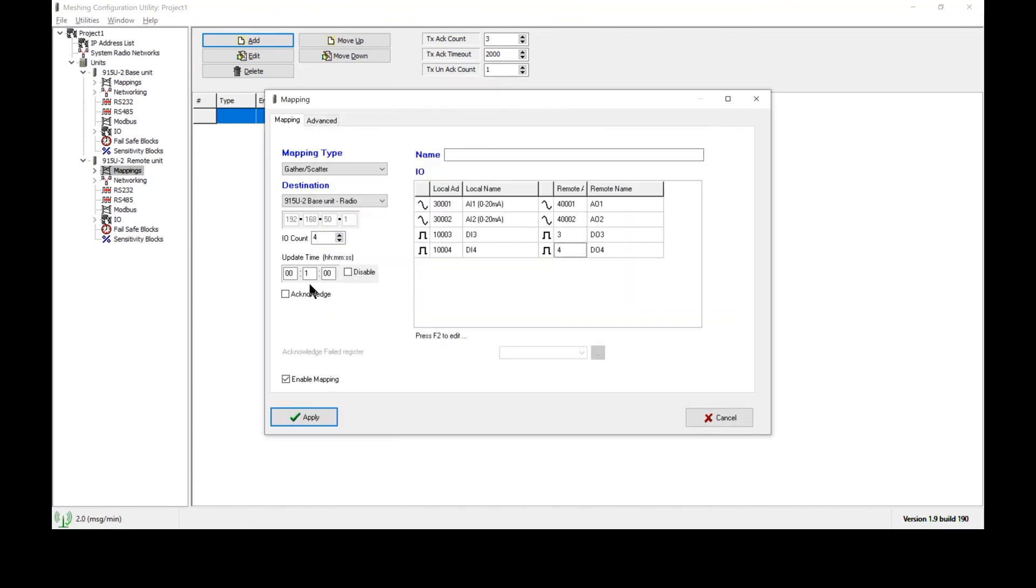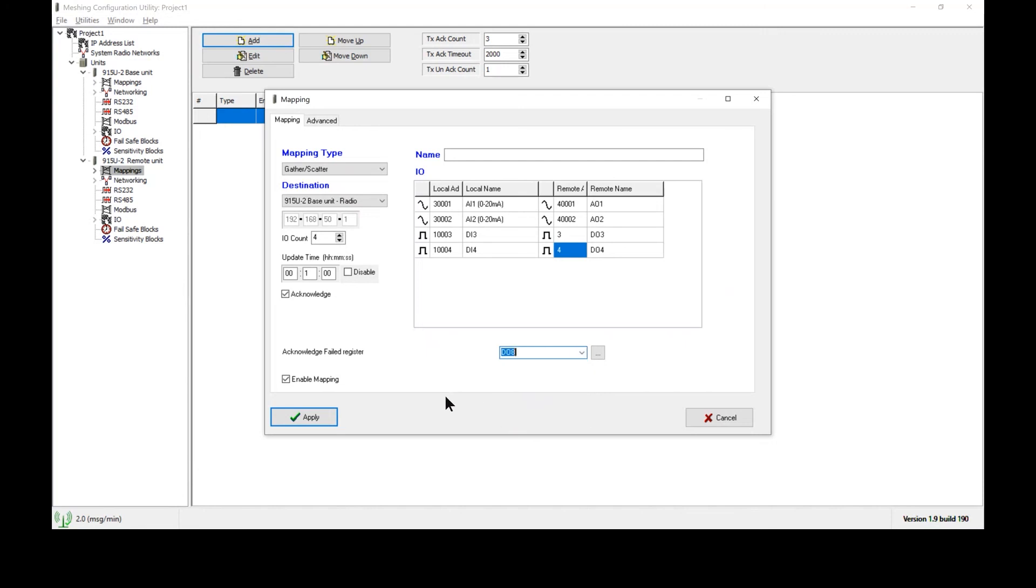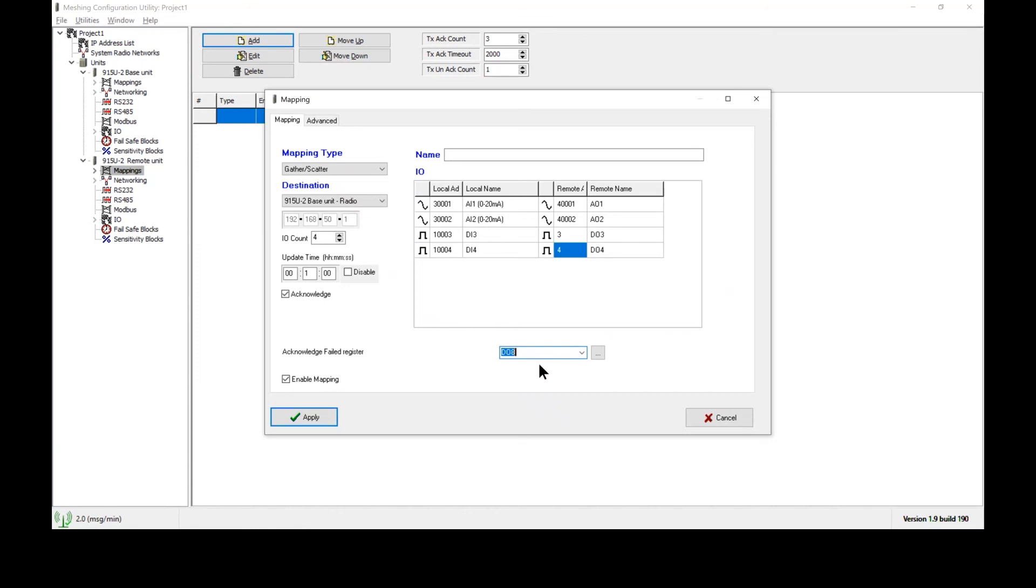And again, I will enable acknowledgement so that we now have a fail register. So, we can very quickly, by observing the status of DO8 or the LED next to DO8 on the terminal block of the radio, determine whether this mapping was functional or not. I will have to remember to wait one minute for this mapping to occur before we determine the status of communications through this LED. As an alternate, we could trigger any one of these inputs here and they will force a transmission to occur within one second. And we will then see the status of DO8 turn off as the radio makes the transmission. The transmission is successful and DO8 is then extinguished.